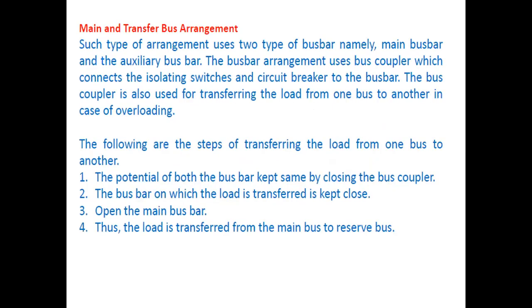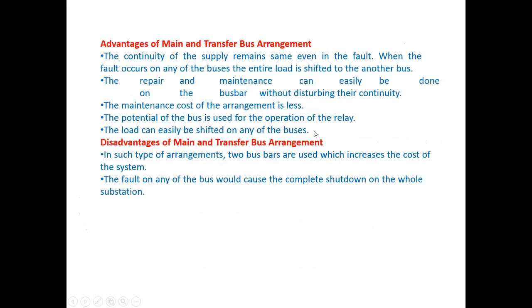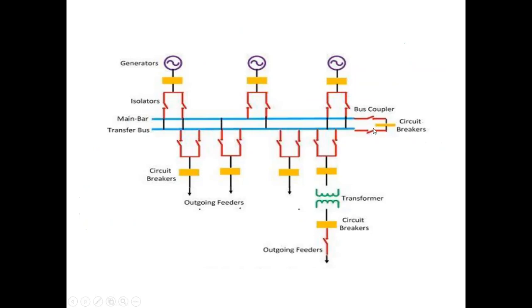The next type is the main and transfer bus scheme, which is an alternative to the double bus bar scheme. Two buses are used: one main bus bar and one transfer bus. If any fault occurs or maintenance needs to be done on the main bus, a bus coupler connects the transfer bus. Outgoing feeders are then connected to the transfer bus. Circuit breakers and isolator switches connect the incoming and outgoing feeders between the two buses.